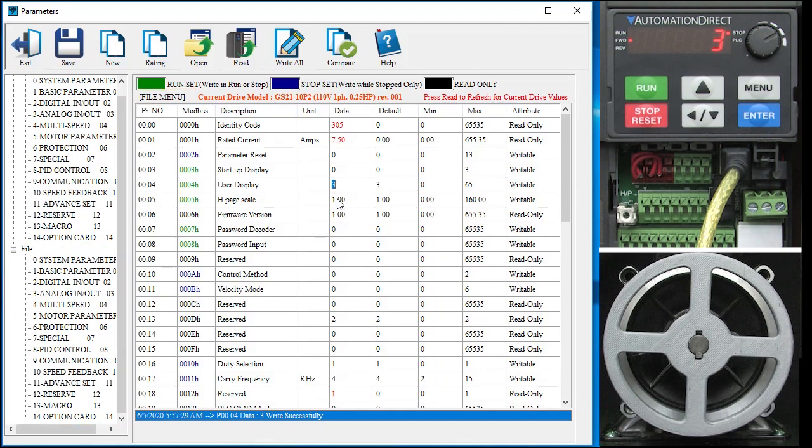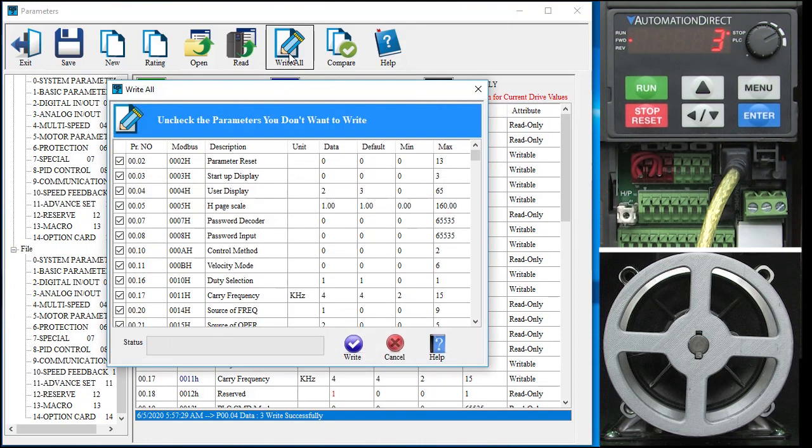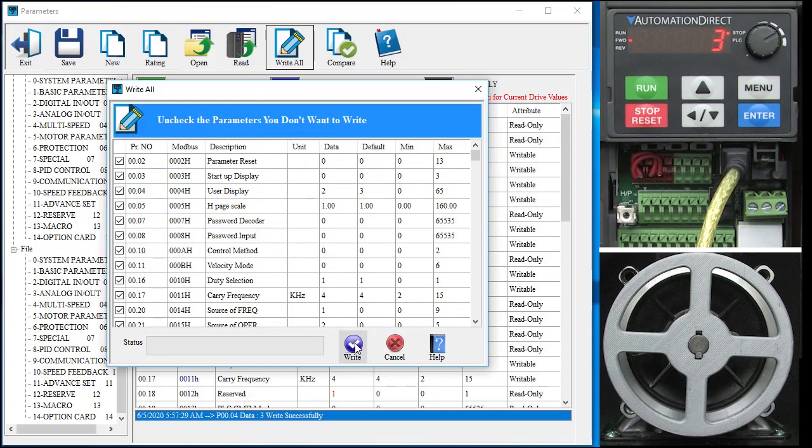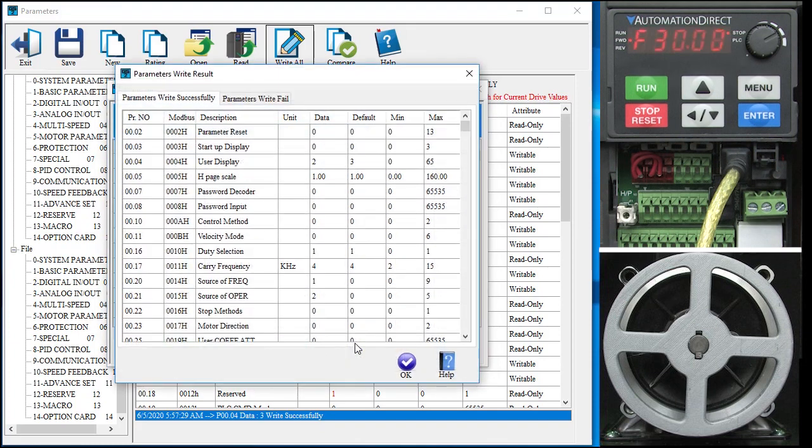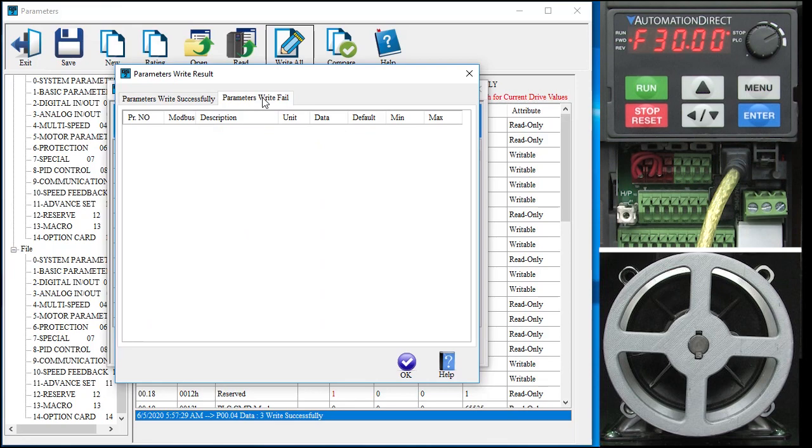Let's change that same parameter back to a 2. The drive didn't change because we are not editing the drive parameters. But, we can write the file parameters to the drive by clicking write. We can deselect any parameters we don't want to write and then hit the write button. When it is done, we see the write summary page where it tells us everything that was written and any parameters that didn't get successfully written.